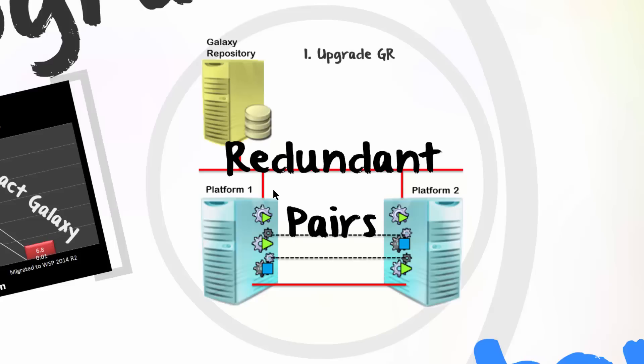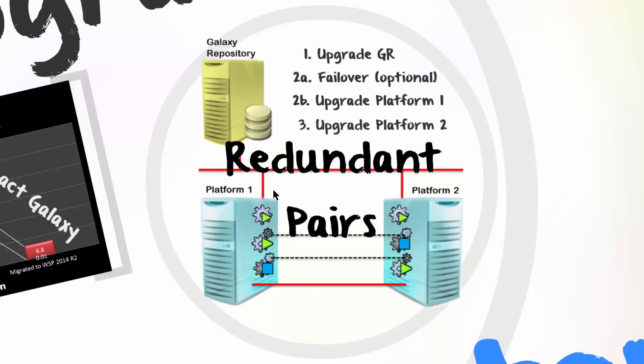Upgrade of a redundant pair is a simple three-step process. First, as usual, the Galaxy repository must be upgraded. Second, you must prepare one of the redundant pairs to be the active running environment by ensuring all engines are active in that platform. You will then upgrade the other standby platform. Third, once upgraded, this redundant pair will become active and you can then upgrade the partner platform.